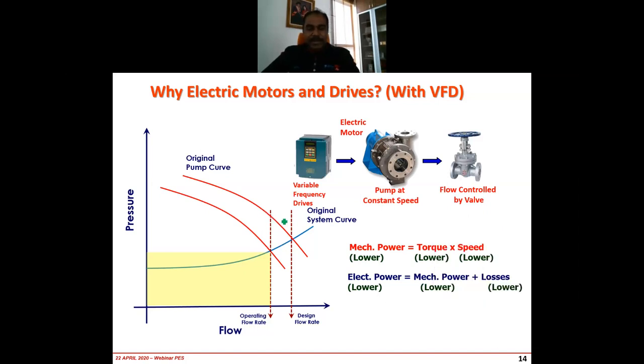So if you notice, the pump curve will be shifted. Why is it shifted? Because we control the pump speed. This particular curve is only true for that particular speed, so once you change the speed, of course, the pump curve will move. Therefore, what you see here is that your operating point is now here. And again, if you notice, the shaded area is going to be smaller.